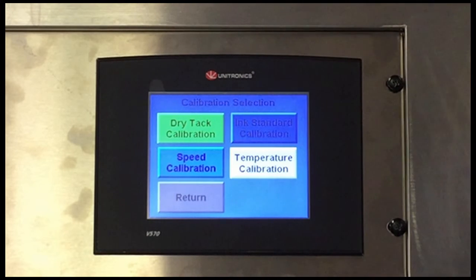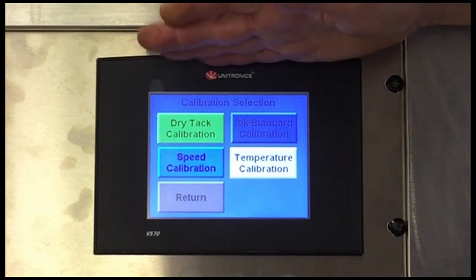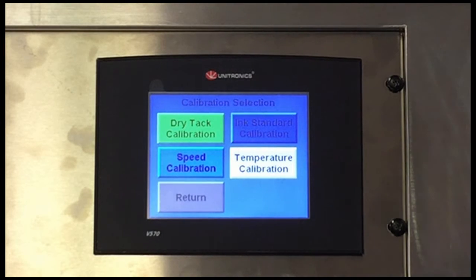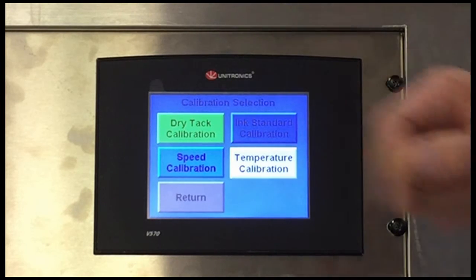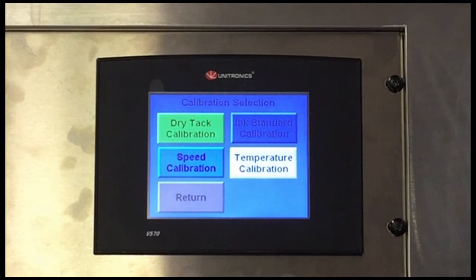The dry calibration we're going to talk about, but I don't know that it's really necessary that we go through the whole procedure. The way the dry calibration is going to work is when we start it, it's going to tell us to install the calibration rig, and there are even some photographs that show how that rig is installed. Then with the rolls turning, it's going to check for 0, and of course the 0 is going to be with the rolls turning with no ink and the ink dry, so you have no tack on the rolls. Then it will tell you to insert certain weights onto the test rig, and now it will figure out what the signal levels coming in are in relationship to those weights. And once you complete that dry calibration, it'll store those parameters, and anytime we run an automatic or a manual test using the dry calibration, it's going to be in comparison to the data that was generated during that dry calibration routine.